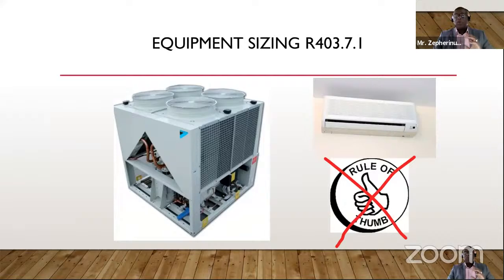And so you have to do actual calculations, taking into consideration the internal loads and external loads to right size the equipment. It may seem a very trivial matter, but in many instances, when you enter buildings, there are people with sweaters on, meaning that you are wasting energy, overcooling the building, and that the same work could be done with a smaller unit. So the code provides you with the requirements as far as how the equipment should be sized based on calculations.